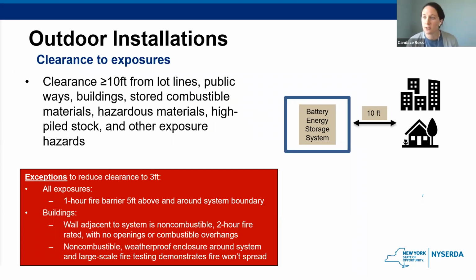All right, so the additional requirements for outdoor systems. There's a requirement for clearance to exposures. Once again, there needs to be over 10 feet clearance from lot lines, public ways, buildings, stored combustible materials, hazardous materials, high piled stock, and other exposure hazards. And you're able to reduce this clearance to 3 feet from all exposures if you have a 1 hour fire barrier 5 feet above and around the system boundary, and then for buildings, if the wall adjacent to the system is non-combustible.